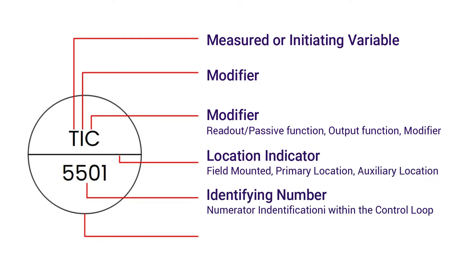Every instrumentation symbol available in the P&ID diagram is like this symbol. First letter indicates measured or initiating variable. Second letter indicates a modifier, it means it looks like an indicator. Third letter indicates a modifier. In this case, it is a controller that is used to provide a manipulated value to the output device. This line indicates instrument location. Identifying number indicates the loop number of the control system. Instrument symbols indicate whether the instrument is used for indication purpose or for interlocking function.